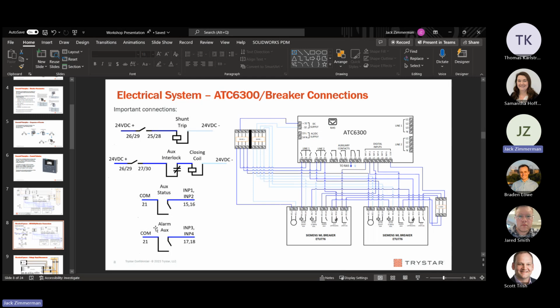And then these are just the auxiliary alarms. You said safety. Do you mean resilience or you mean safety? So if both breakers close at once, that could put out-of-phase generator and utility on the same line, which can cause massive waveform distortion, which can cause damage to our equipment, damage downstream, or malfunction. Look at the punch. If we fed the punch out on the floor dirty power, it could malfunction in a way that could be dangerous to people. So that's why it's a safety mechanism. Even though it's not super obvious, clean power is safe power, right? That's important.